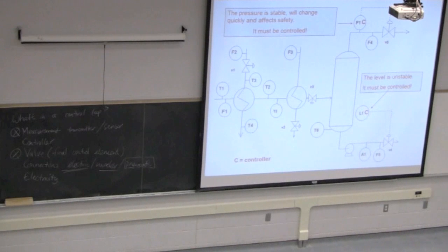Is saying open. Okay, valve should fail open. Why? We don't want this buildup of pressure occurring. If there's a plant failure, we want to let that pressure out of the drum. We don't want to have a pressurized vessel beyond our level.